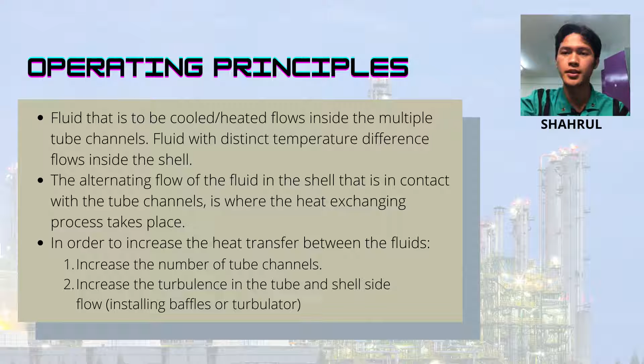In order to increase the heat transfer between the fluids, you can either increase the number of tube channels, which further increases the exposed surface area and the heat exchanging process, or increase the turbulence in the tube and shell side flow by installing baffles or a turbulator, which also further increases the heat exchanging process. Now I will pass to the next presenter.